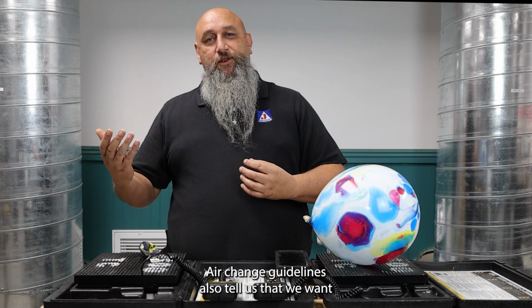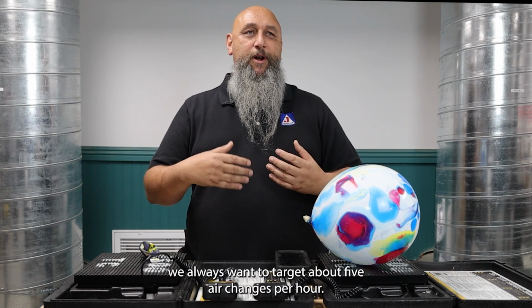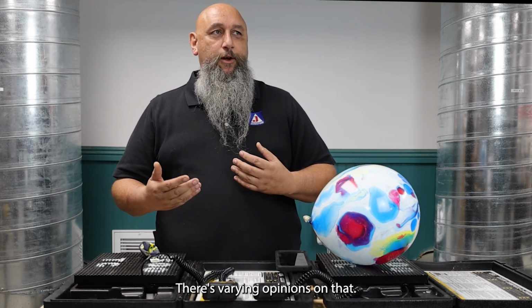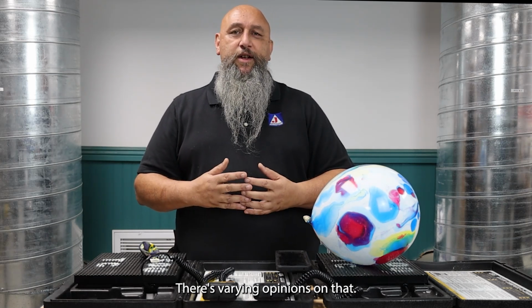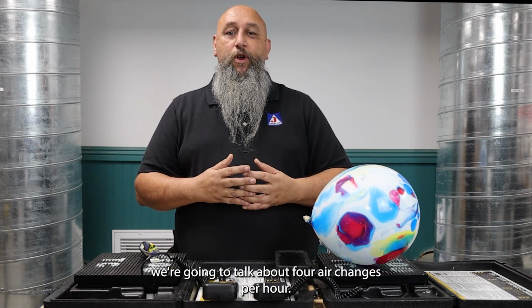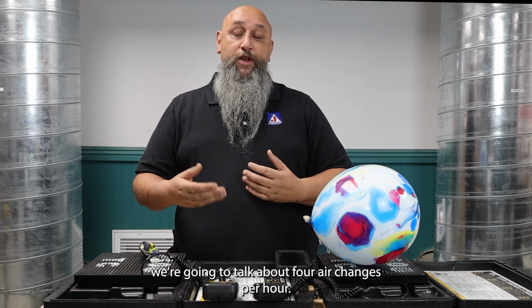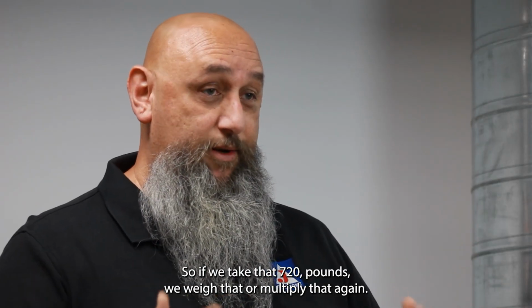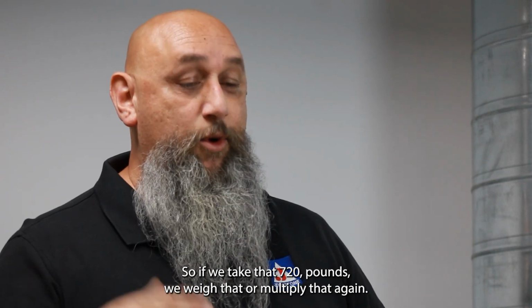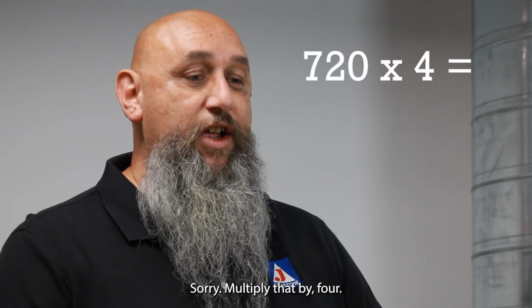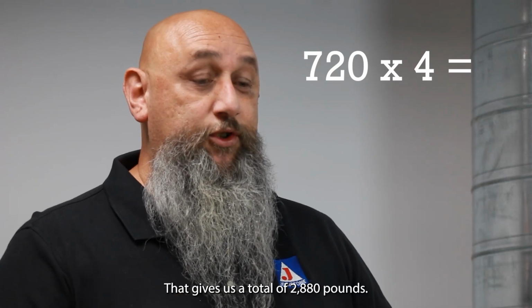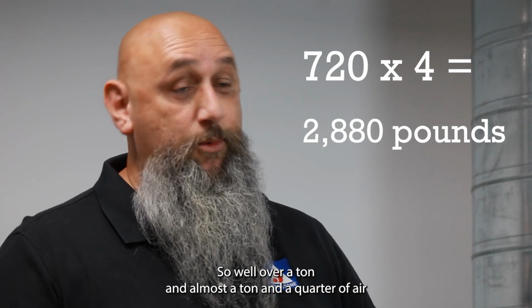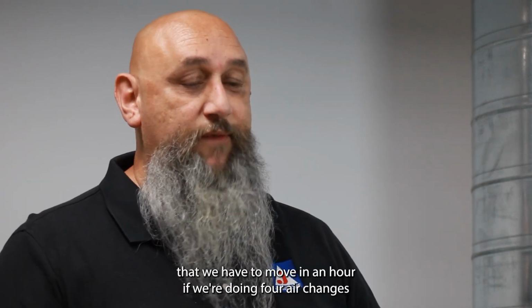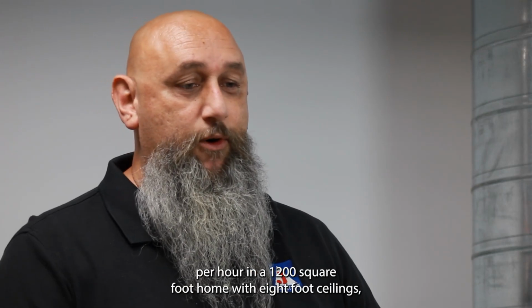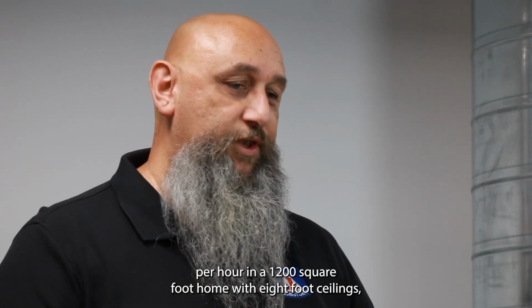Air change guidelines tell us that we want to target about 5 air changes per hour. There are varying opinions on that, but for the purposes of what we're doing today, we're going to talk about 4 air changes per hour. So if we take that 720 pounds and multiply it by 4, that gives us a total of 2,880 pounds. So well over a ton, almost a ton and a quarter of air that we have to move in an hour if we're doing 4 air changes per hour in a 1,200 square foot home with 8-foot ceilings.